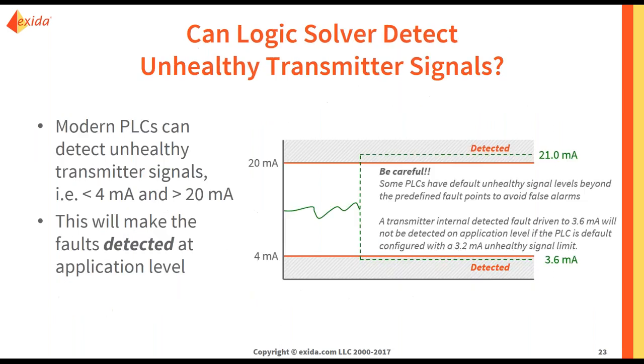You have to keep in mind whether your logic solver can detect unhealthy transmitter signals. Modern PLCs can detect unhealthy transmitter signals, which will make the faults detected at the application level. However, if your logic solver does not know that your transmitter detected an internal failure, this would be classified as an undetected failure. So this is something to look into.